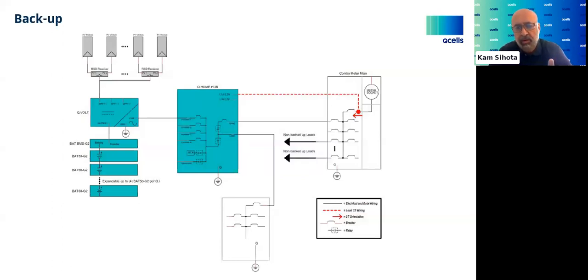In this case, we've removed the external CT meter because that meter now sits inside the hub - we have a revenue grade meter inside the hub. That's where the automatic transfer switch is, which isolates the home from the grid during a power outage and flows power from the battery to your loads.